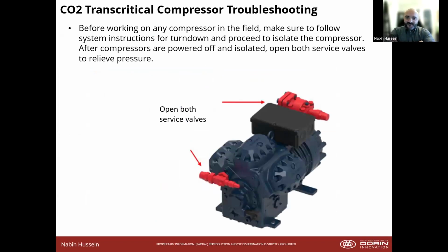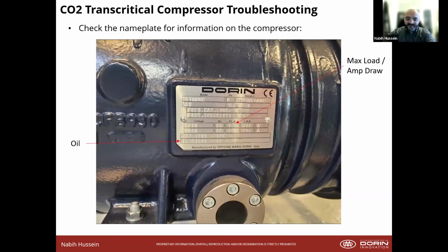This troubleshooting section, I have brought it down a little bit from my typical. At an NASRC event, we would go into this troubleshooting section and that would be coupled with a compressor teardown. But I've brought this section down to just typical safety devices you would see on a compressor. So if you come up to a compressor, first thing, you look at the nameplate. It will tell you what oil it's using, its max load amp draw, quick things to check, and then the oil sight glass to make sure that the oil level is at 1/3 of that.